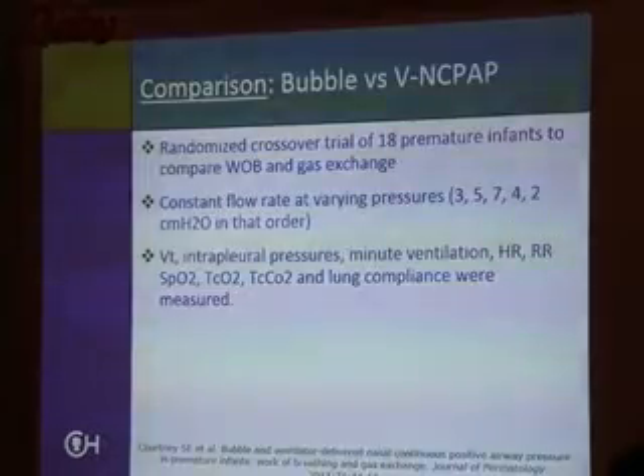And what they saw was that the intraprong pressures for bubble CPAP were flow dependent, just like we saw in some of the past studies and the bench studies. As the flow rate was increased, the average intraprong pressure was 1.3 centimeters of water pressure higher than set, pretty constant. And we saw that in one of the last bench studies as well, that it was up by about 1.3.